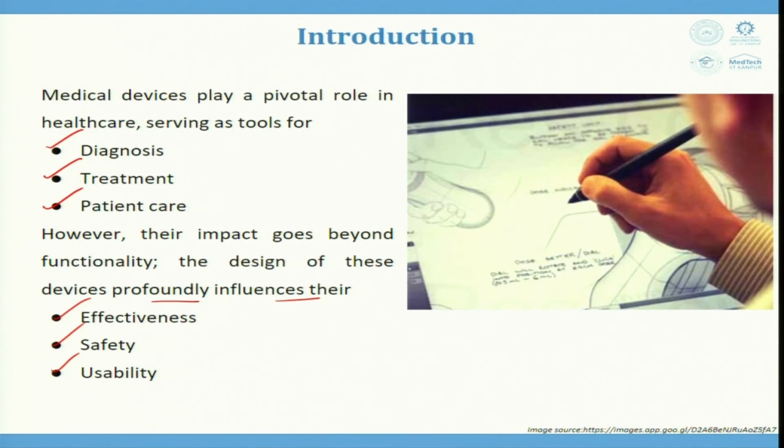Safety is always associated whenever we are talking about medical devices, because medical devices are designed based upon a quality management system. We will discuss ISO 13485, which is a quality management system that pertains to keeping the record of who designed, who performed certain operations on designing these medical devices, what materials were used, where the materials come from, and whether the biocompatibility of the material is correct or not. All these things are kept into account so as to record what the risk is if something fails. Based upon this, safety is always taken into account.